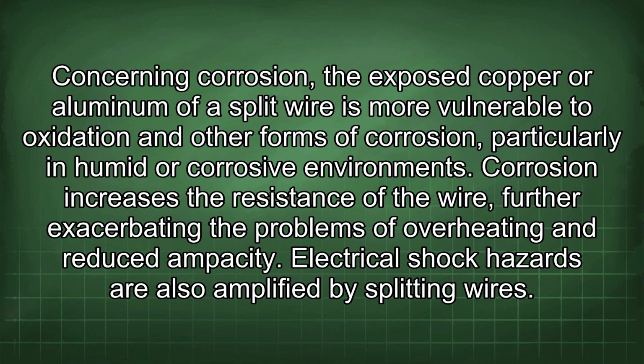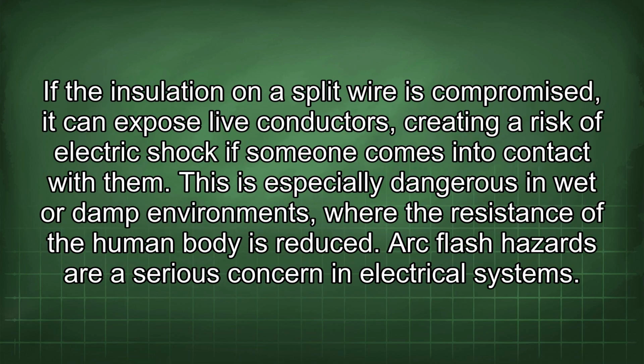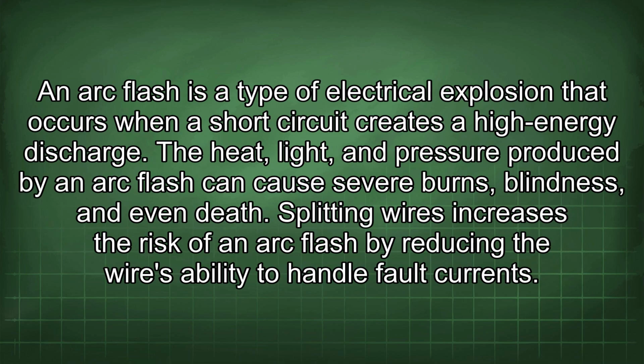Electrical shock hazards are also amplified by splitting wires. If the insulation on a split wire is compromised, it can expose live conductors, creating a risk of electric shock if someone comes into contact with them. This is especially dangerous in wet or damp environments, where the resistance of the human body is reduced. Arc flash hazards are a serious concern in electrical systems. An arc flash is a type of electrical explosion that occurs when a short circuit creates a high energy discharge. The heat, light, and pressure produced by an arc flash can cause severe burns, blindness, and even death.